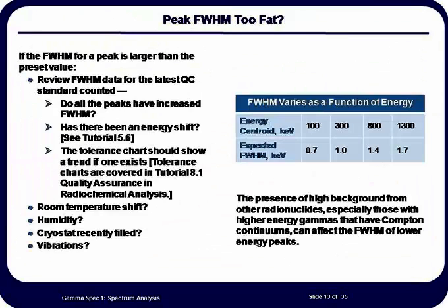In most cases, you will find that there is an environmental effect in the laboratory responsible for the poor peak shape. However, if there is no conclusive evidence that this was the cause, chemical separation may need to be performed for the analysis of that radionuclide to remove or mitigate the effect of the interfering radionuclide's gamma ray.